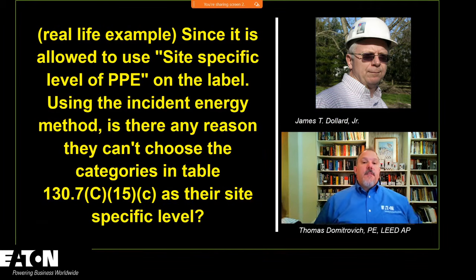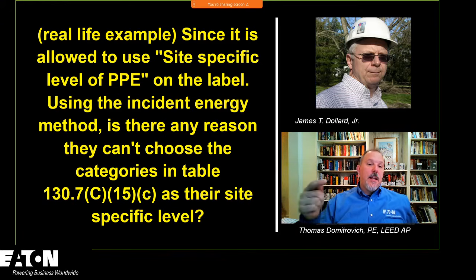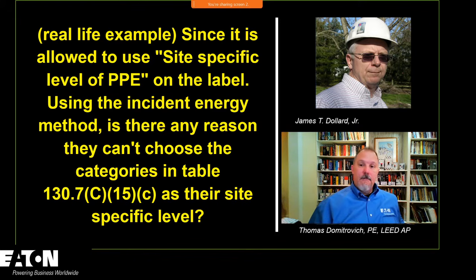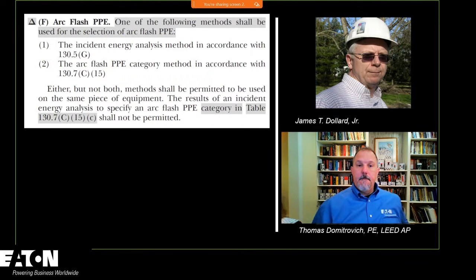This is a real life example. It says, since it is allowed to use site-specific level of PPE on the label using the incident energy method, is there any reason they can't choose the categories in table 130.7(C)(15)(c) as their site-specific level? That is specifically prohibited, and I think we actually added that into the next slide. And we can take a look at the last paragraph there in 130.5(F).